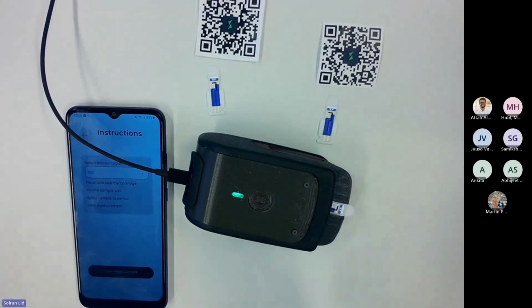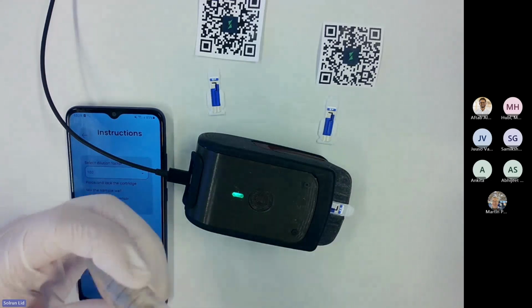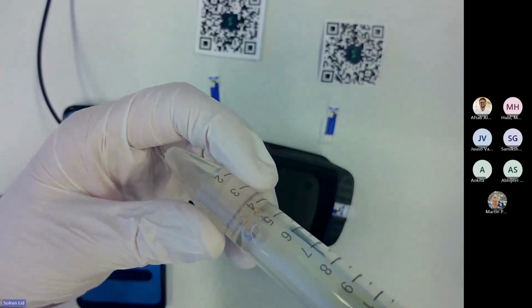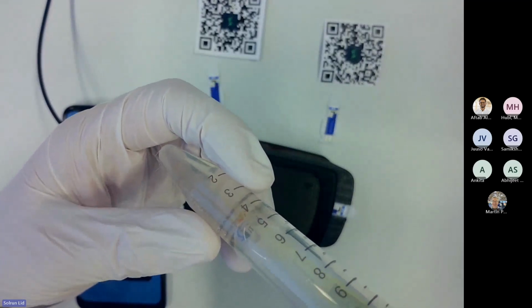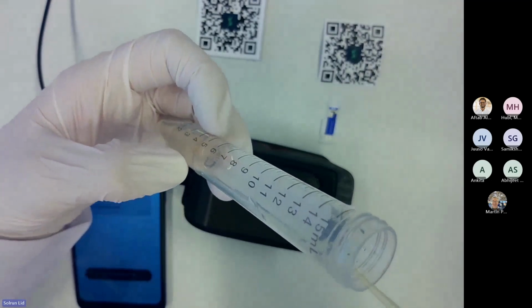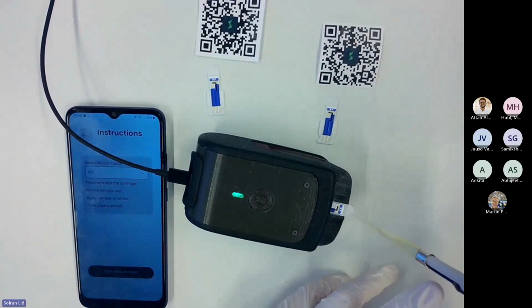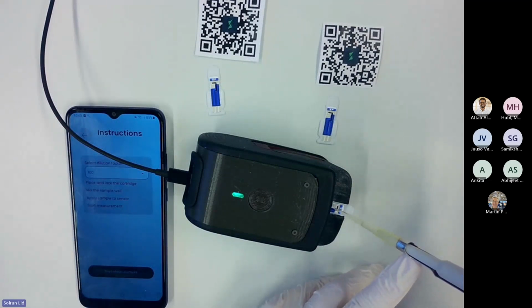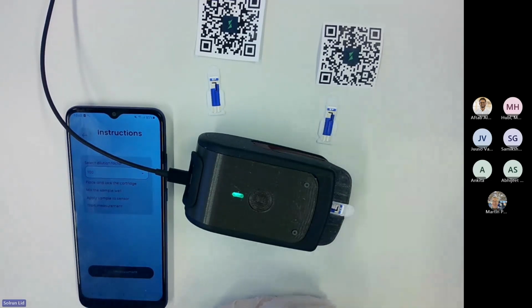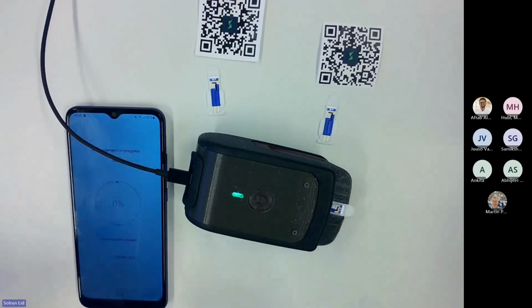So I'll place and lock the cartridge. I'll mix the sample. So next up is to apply the sample to the sensor. So again, I will apply 50 microliters of the sample. Oh, I will actually show you how I pipette. So just like that, just go into the middle of the solution, and I pipette. So now I will apply it onto the electrodes of the sensor, just like that, and be careful not to scratch the electrodes. And then I will click Start Measurements.